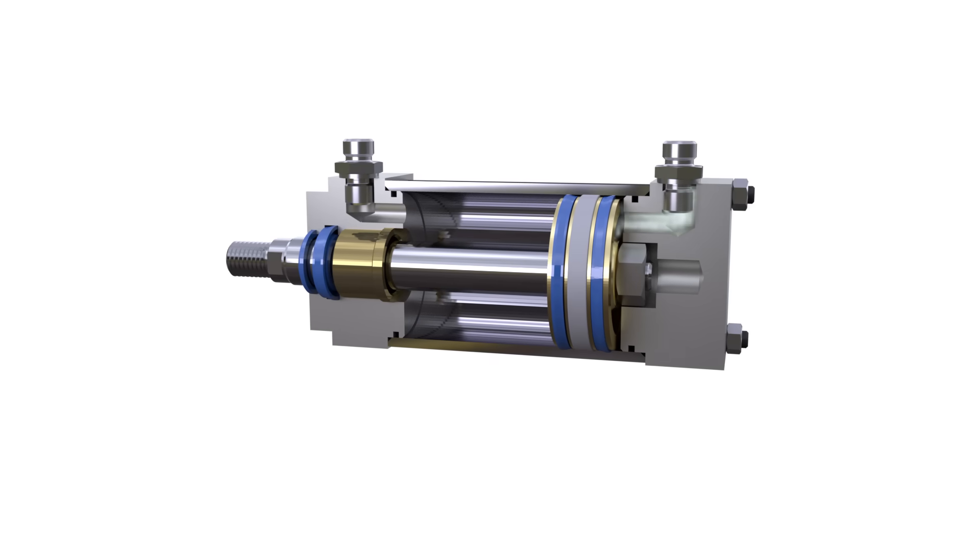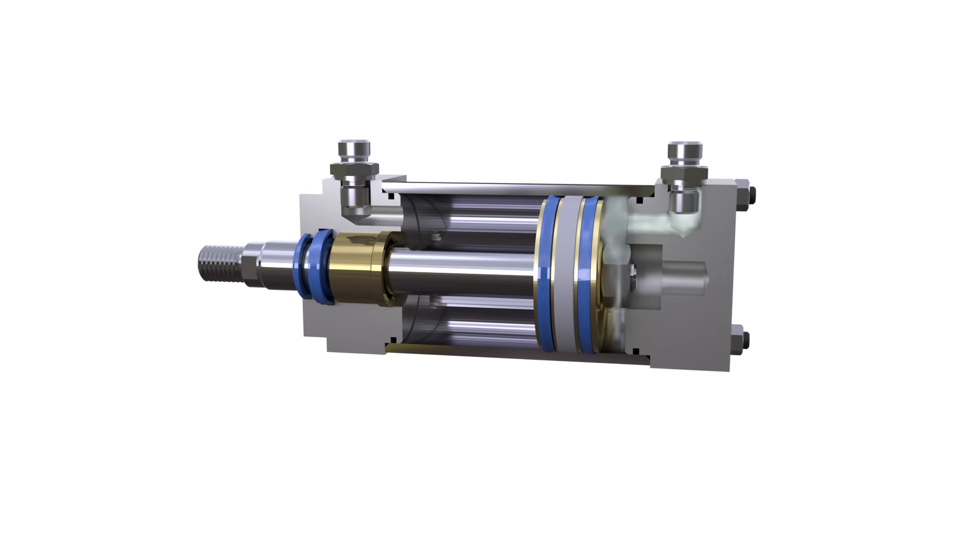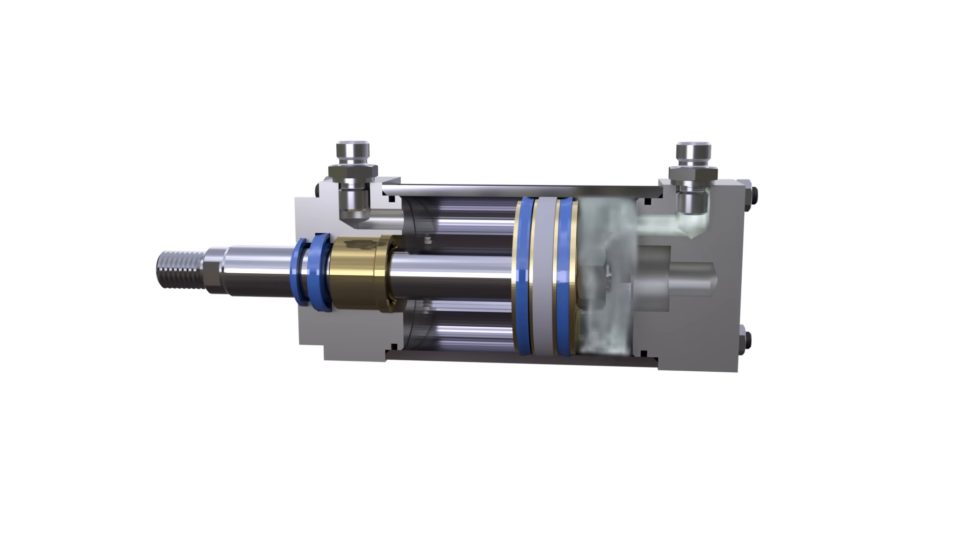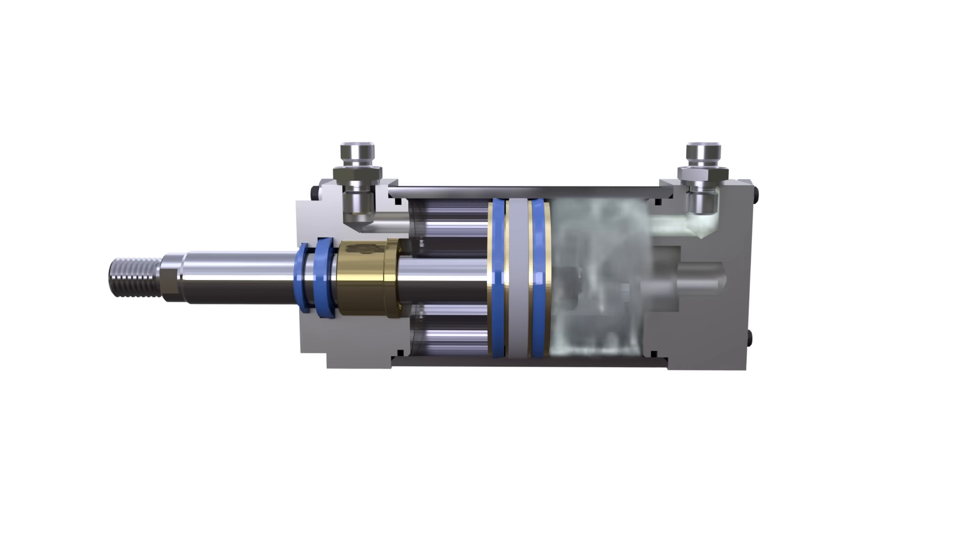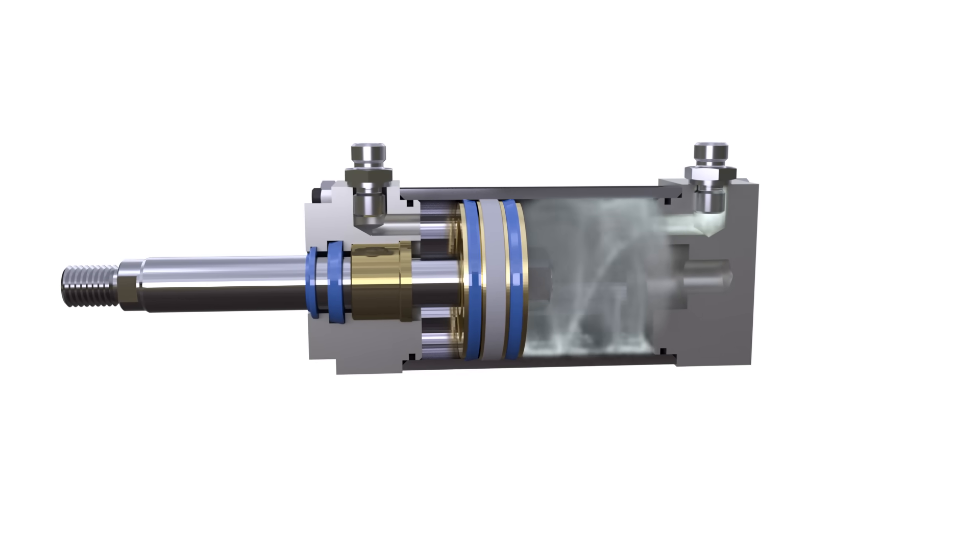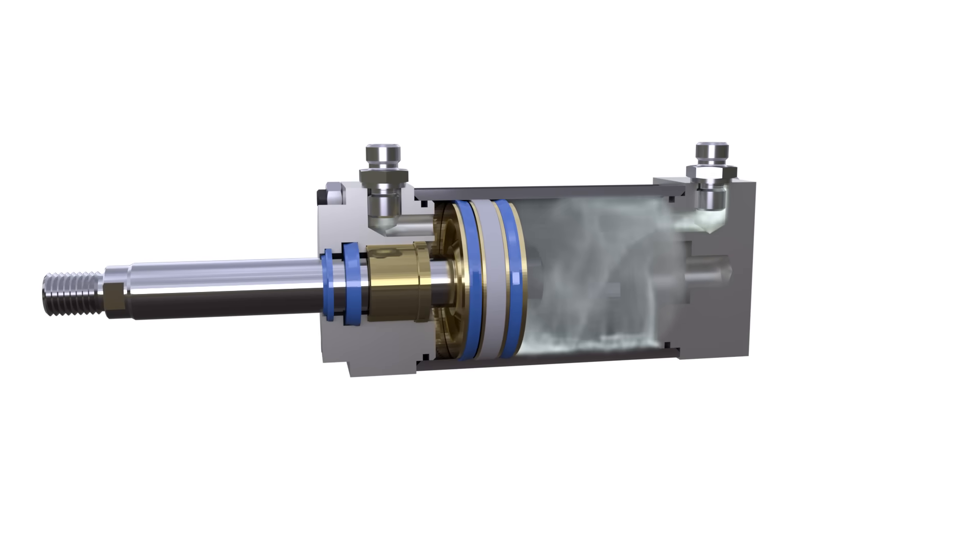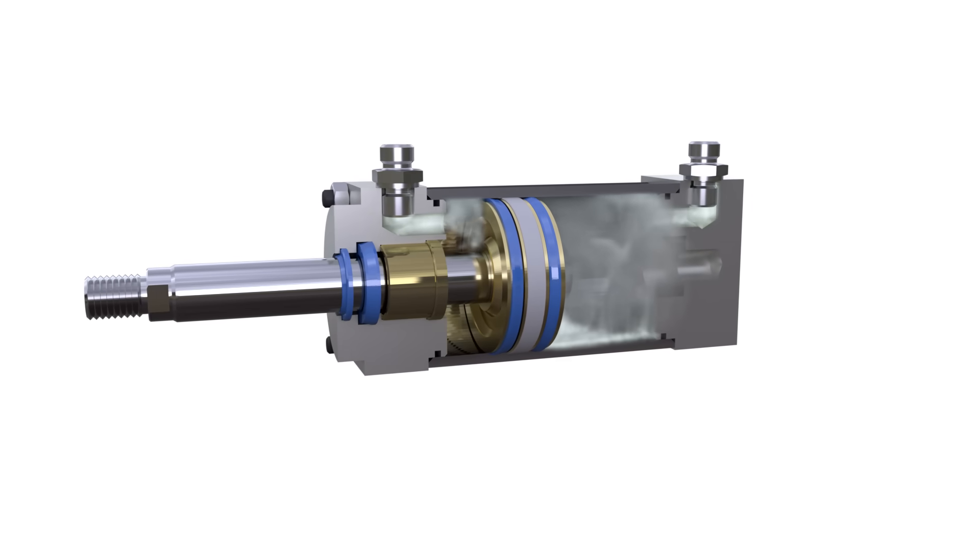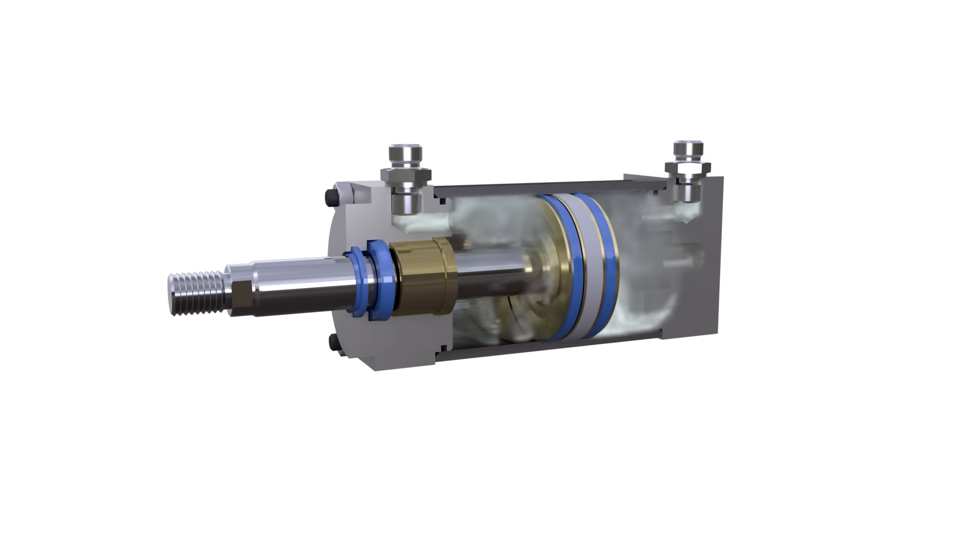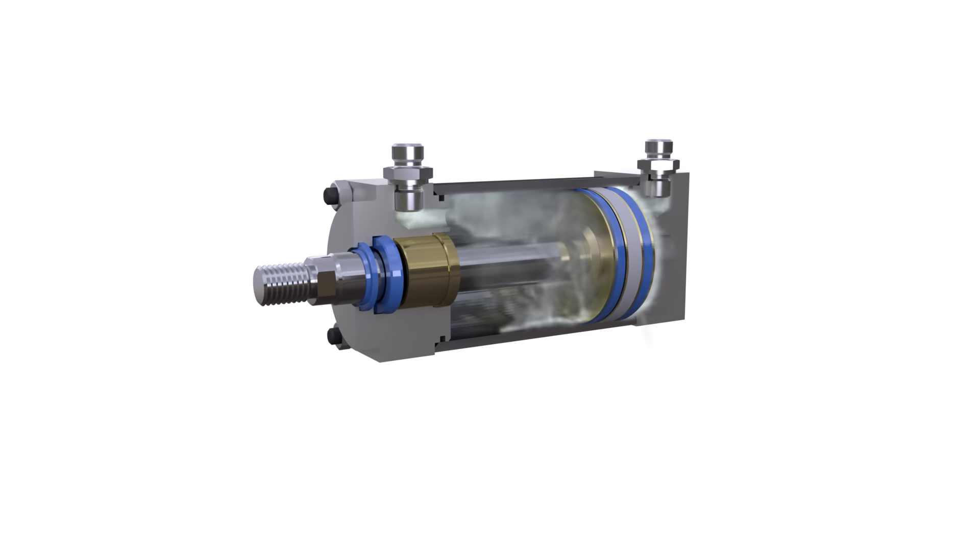In double-acting pneumatic cylinders, air affects the piston from both sides. When introducing air into the piston cavity, air from the rod cavity is sent to the atmosphere, thus making the rod extend. To retract the rod, you need to supply compressed air to the rod cavity and connect the piston cavity to the atmosphere.